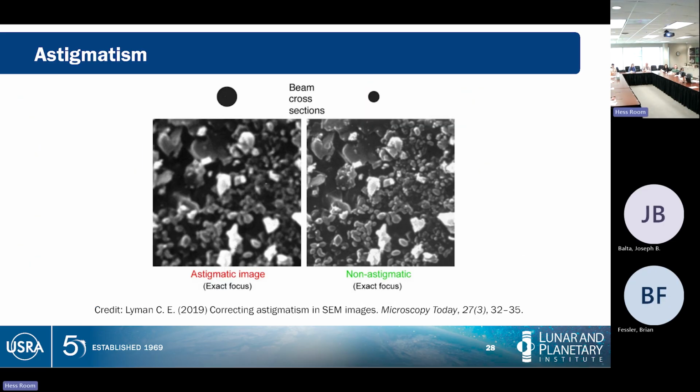There are what are called stigmator coils. Stigmator coils are an extra set of magnets in the line where you can adjust the current through these magnets to account for any distortion that has shown up. Astigmatism is thus an inability to focus fully, and you have extra magnets to help you correct that in basically every electron microscope.